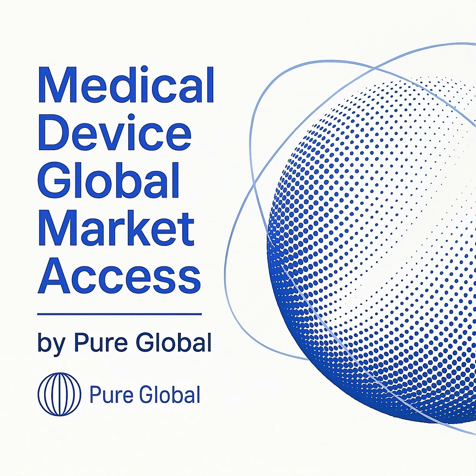The actor module is for registering economic operators like manufacturers, authorized representatives, and importers to receive a single registration number, or SRN. The UDI and device module is the core of the system, where all devices must be registered with their unique device identification data. The Notified Bodies and Certificates module provides a central repository for all issued certificates, increasing transparency. Finally, the Market Surveillance module is for use by competent authorities to coordinate their oversight activities.